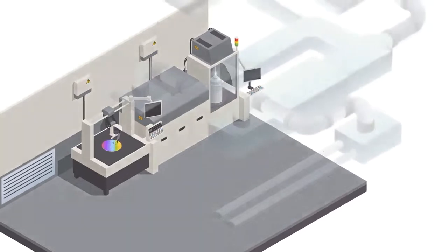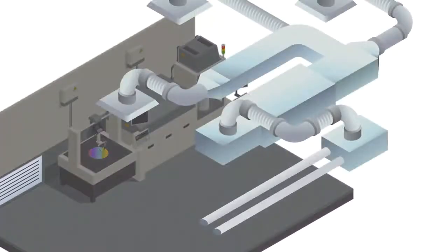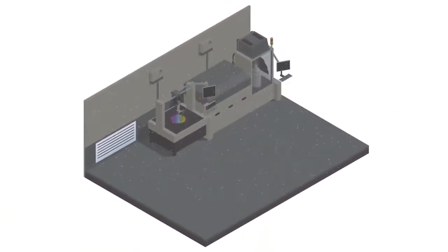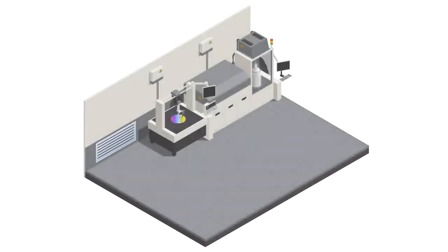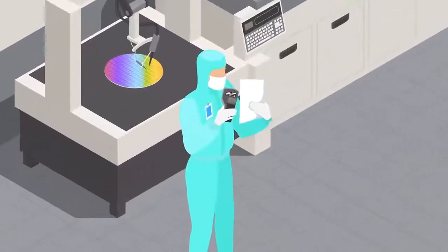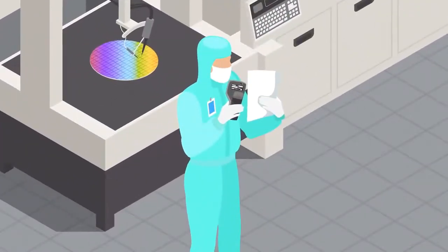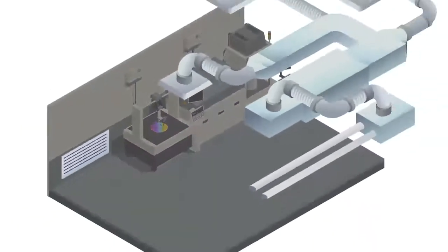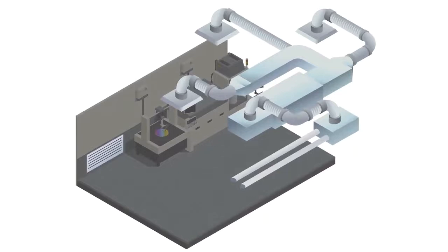There are a couple ways to set up a ventilation system for a clean room, but regardless of which system is used, the purpose is the same: to remove contaminants so the environment stays clean and controlled. To ensure your ventilation system is working properly, it's important to check the quality of airflow by taking measurements and comparing them to the expected performance of an optimal system. However, picking a device that can get the measurements you need will depend on the ventilation setup. For the purpose of this video, we'll look at the 2 most common ventilation setups and see how the Kanomax Climomaster anemometer can be of use.